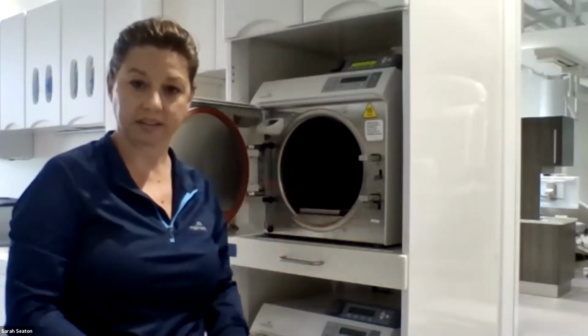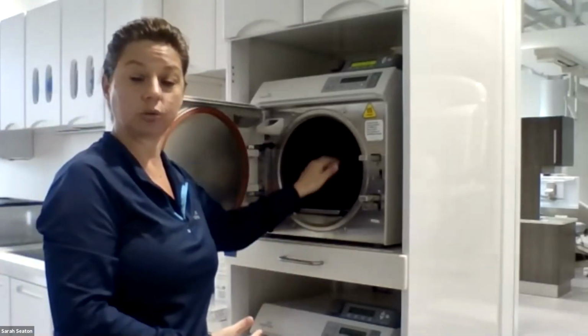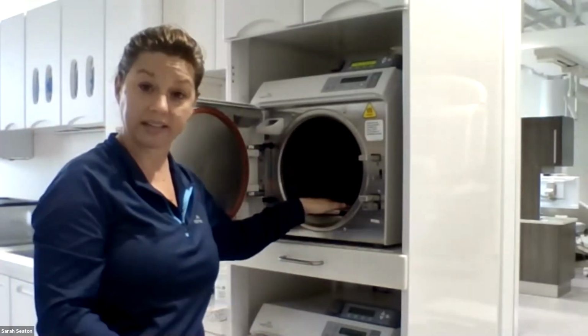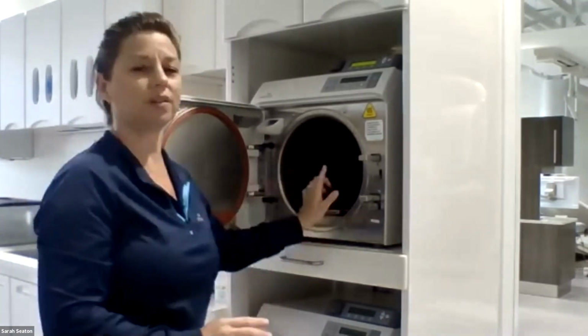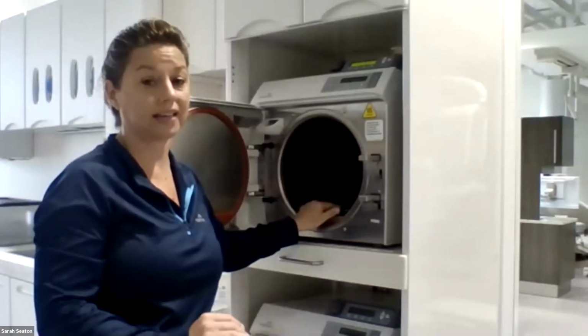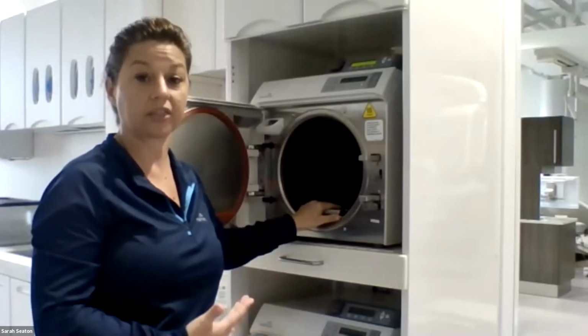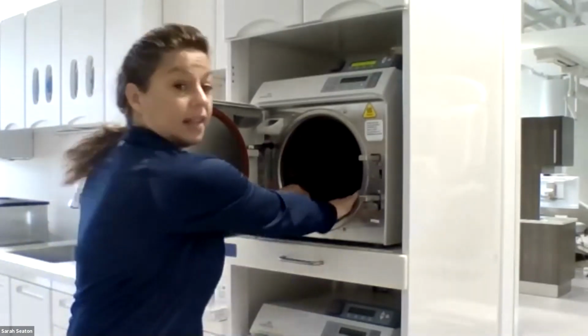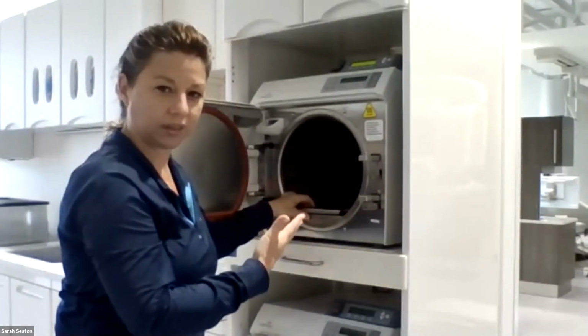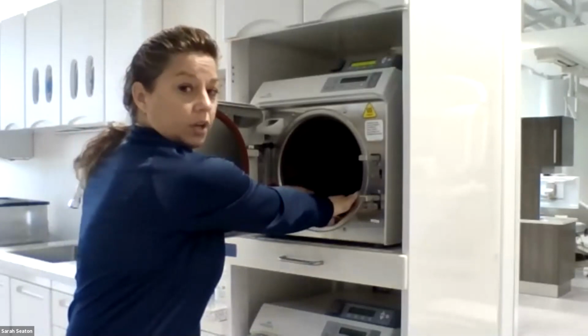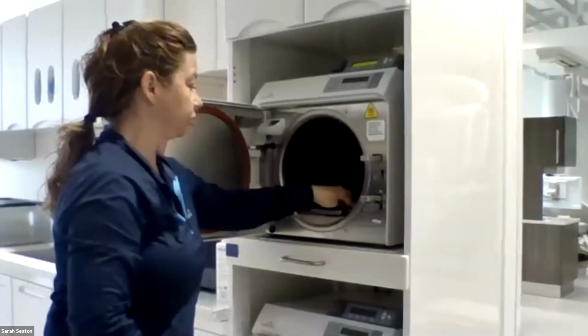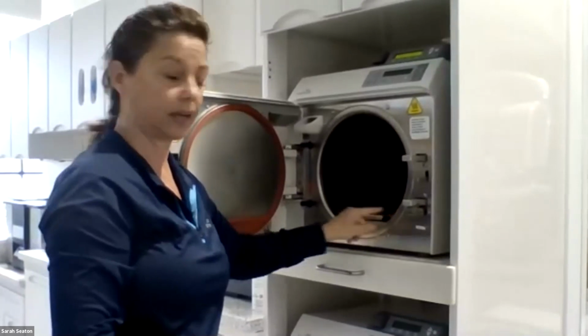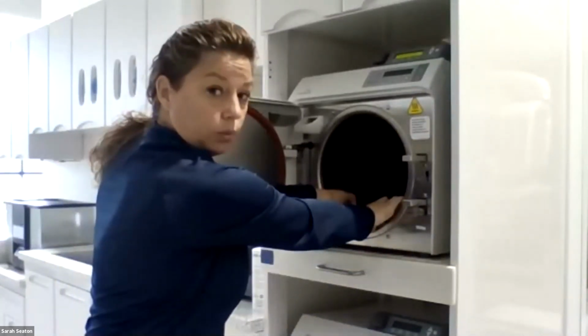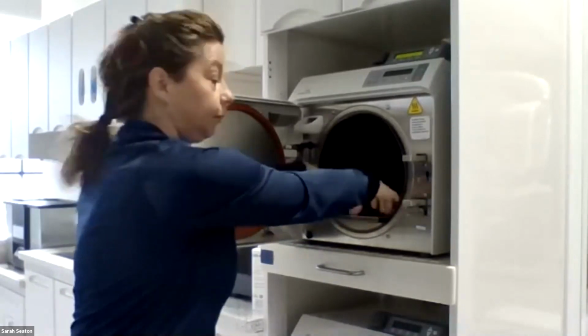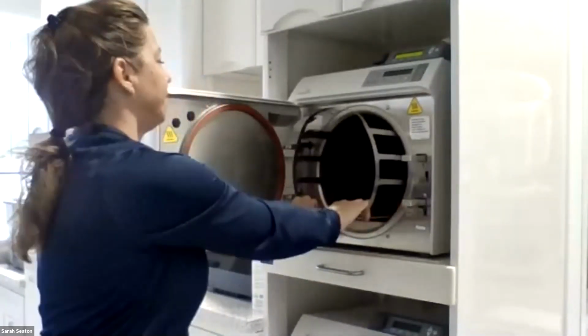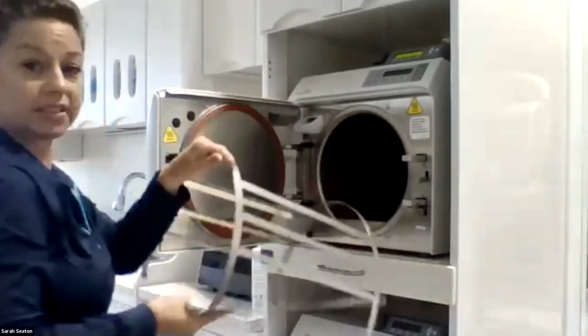So once you've drained your reservoir, you want to take your trays and your racking out. Now this already has the trays out, but it's important that you also take the tray plate and racking out as well in order to do that thorough cleaning inside the chamber. It's very easy to do. Some people are kind of intimidated by it. What you want to do is you'll see some holes along the edges of your tray plate. Go to like the second one back, lift up and pull out towards you, and it comes off very, very easy, just like that.